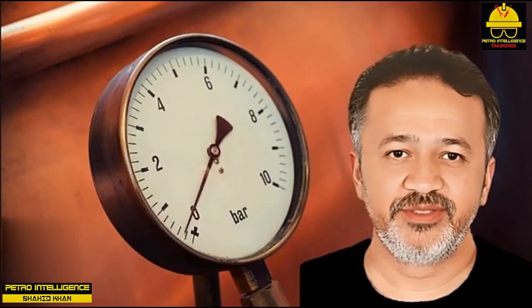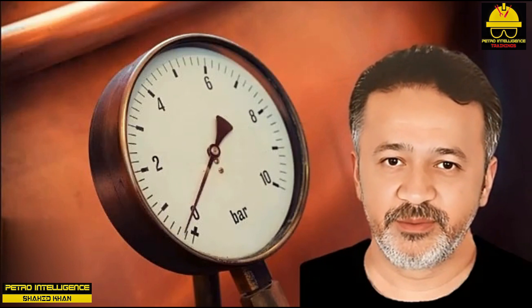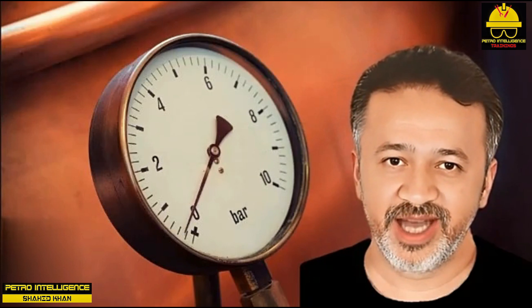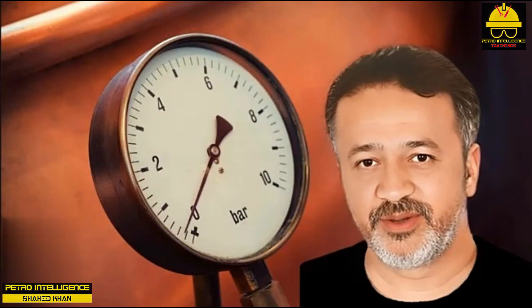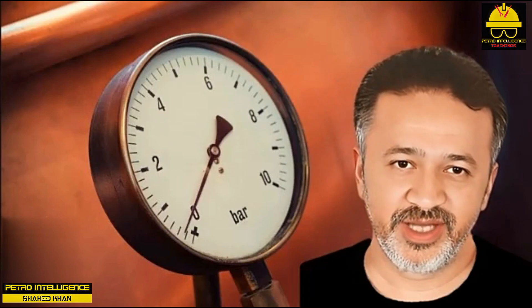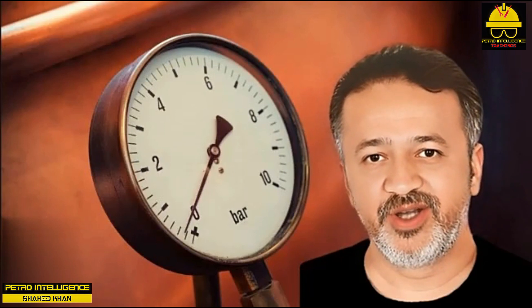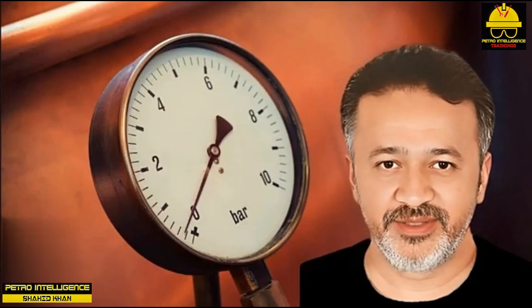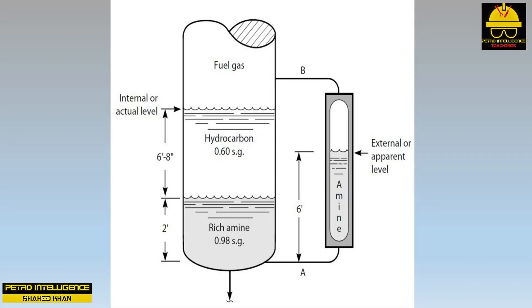Level indication: what is the difference between a gauge glass and a level glass? Simply, there is no such thing as a level glass. The liquid level shown in a gauge glass does not correspond to the level in a process vessel. This picture is a good example — this is the bottom of an amine fuel gas absorber, a tower used to remove hydrogen sulfide from the fuel gas.